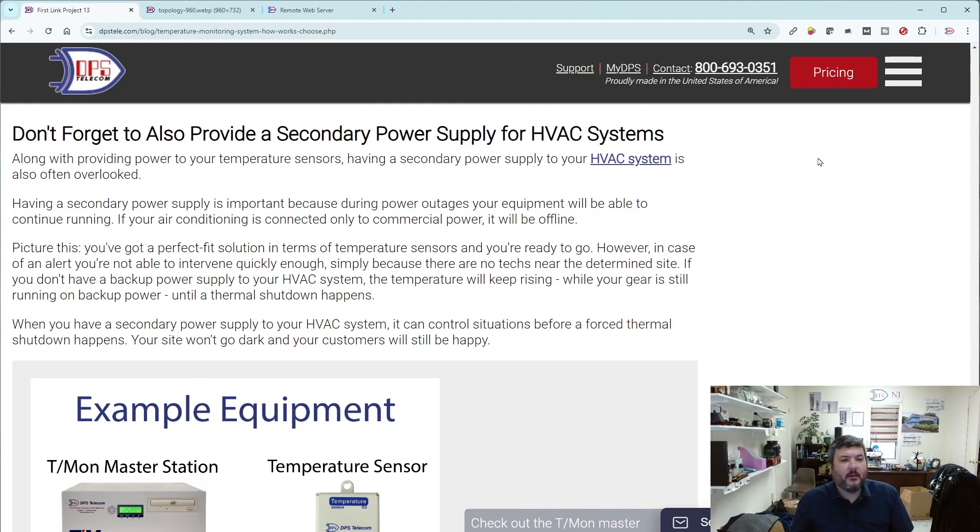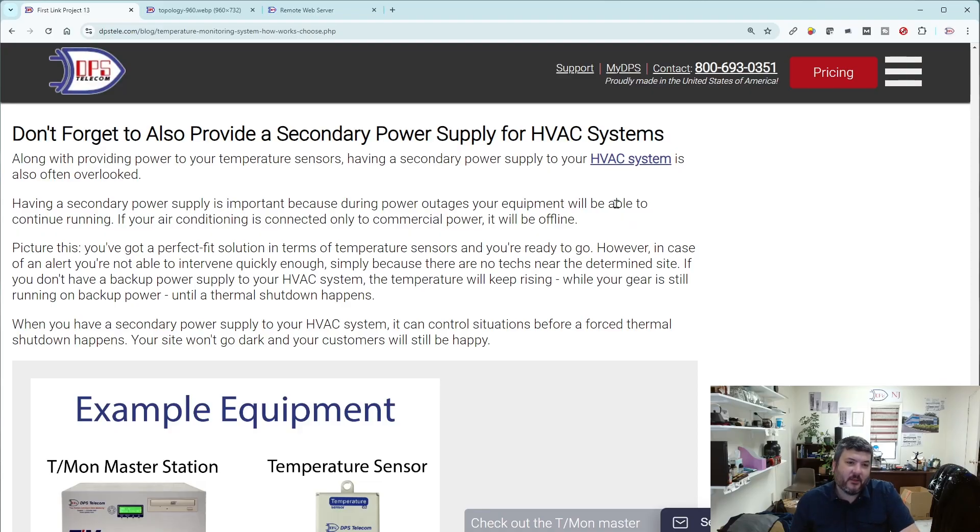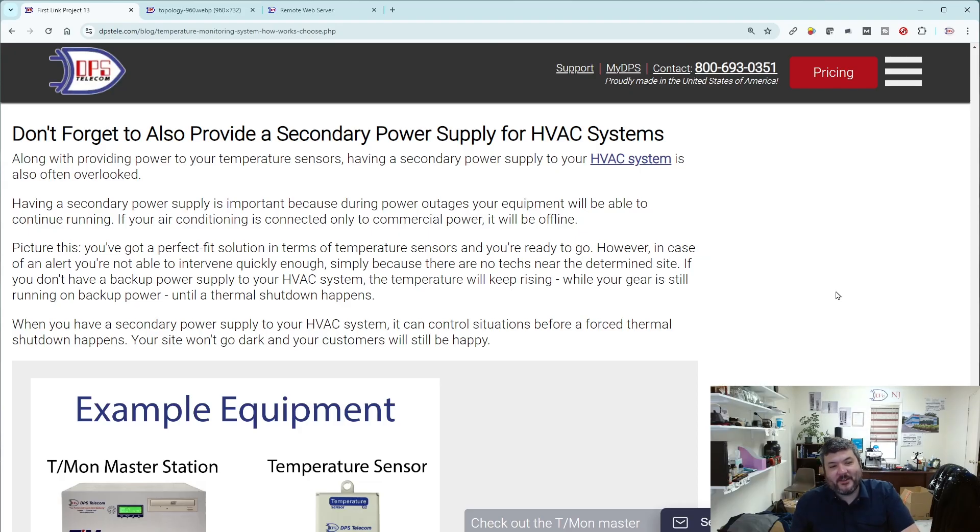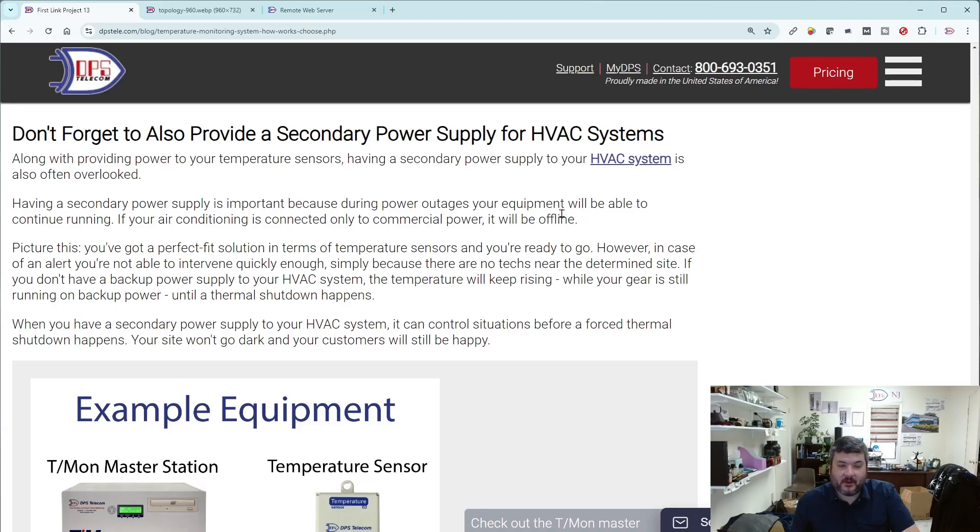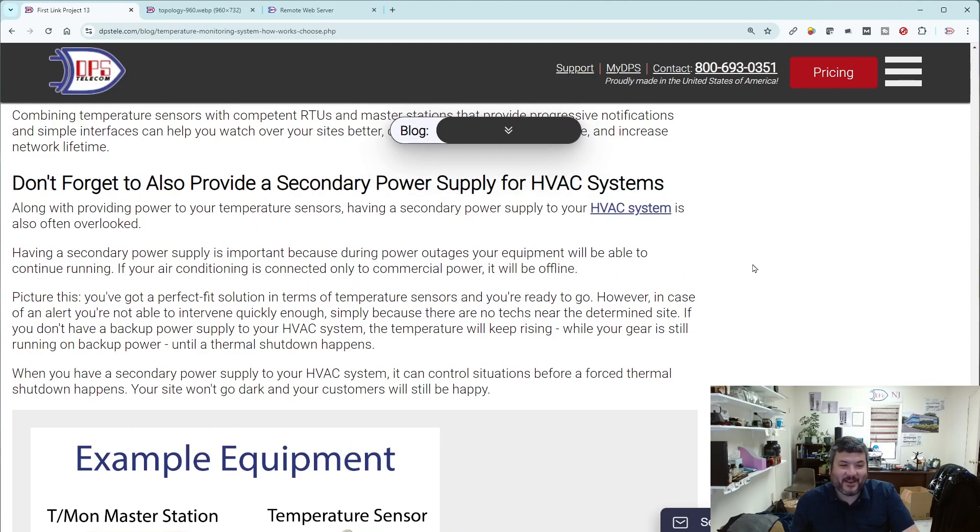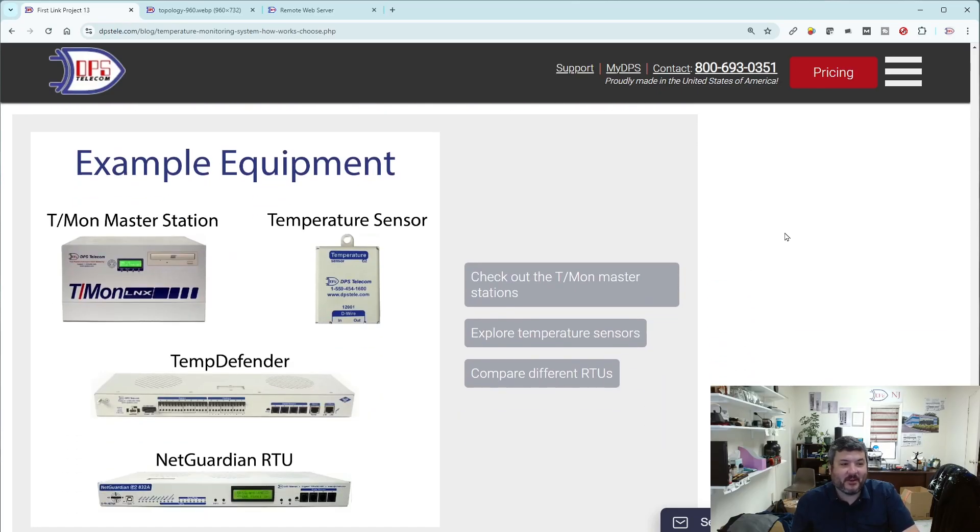If we look at HVAC systems, you have to think about powering those things. Once on our website, our web host was off-site. We got a message that there was somebody who crashed into a power transformer in Texas. They shut down power to the data center, which was okay because we had plenty of backup power. But there was no backup for the HVAC system. That presented a problem that they weren't able to keep the cooling system going and the site overheated and had to shut down. Do think about that when you talk about your HVAC system. Keeping your temperature in check will be accomplished better if you have a backup power system for your HVAC system. Size your UPS batteries appropriately for that. Think about generators in the same way.